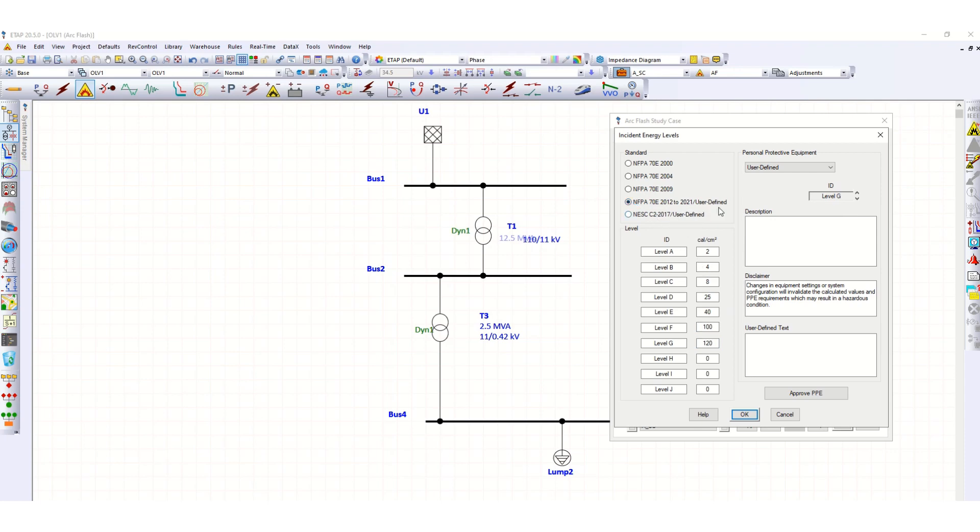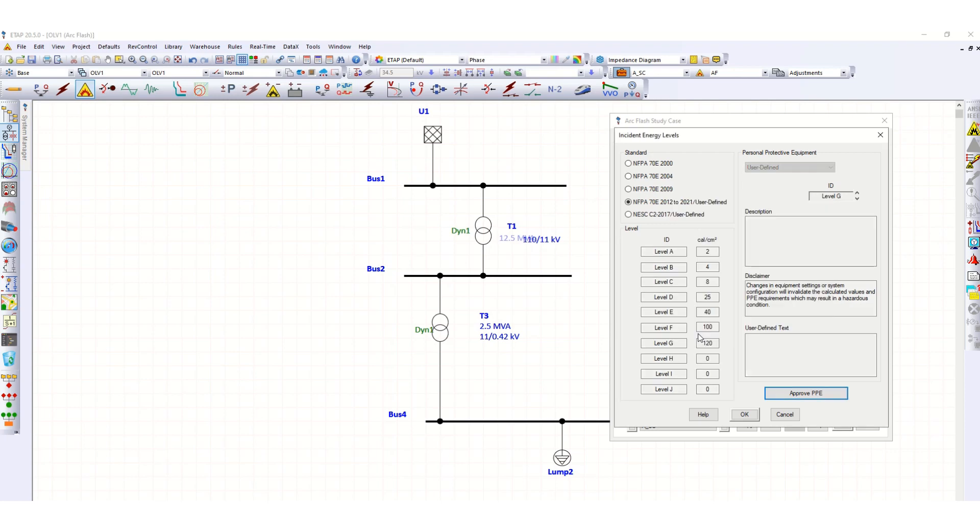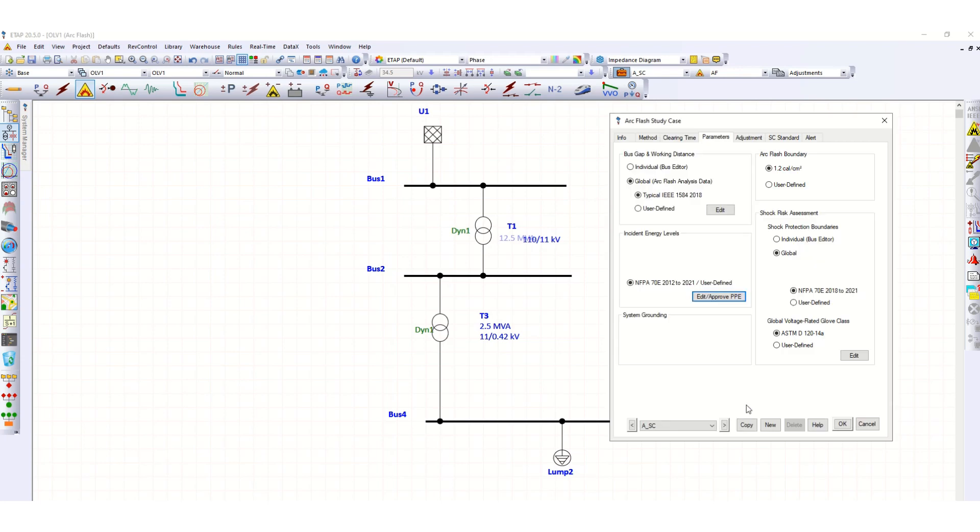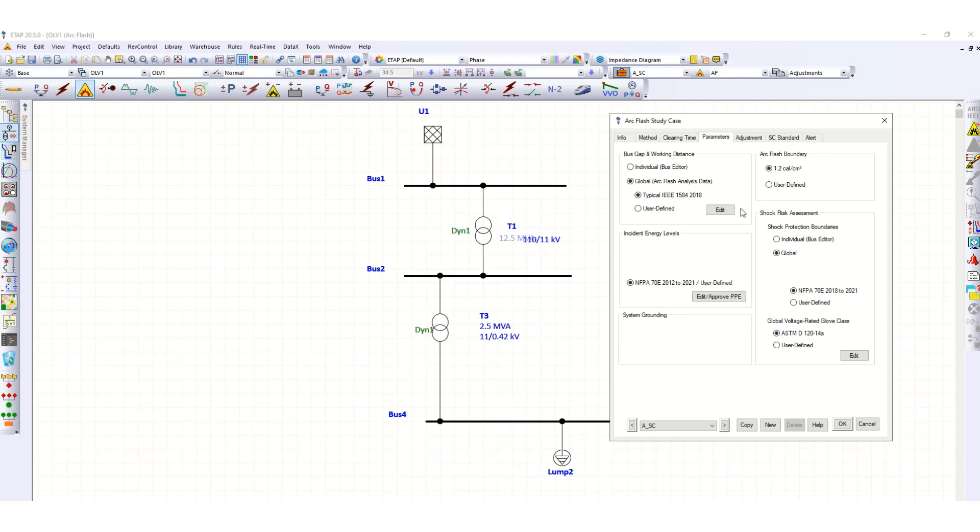You can modify the values also. These are the typical values. For approved PPE, this is personal protective equipment requirement, check this box. Arc Flash boundary uses standard values defined as 1.2 calories per centimeter square. Shock protection boundaries is global as per NFPA 2018 to 2021.